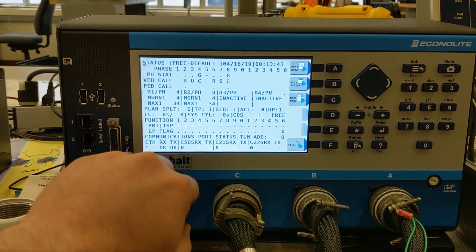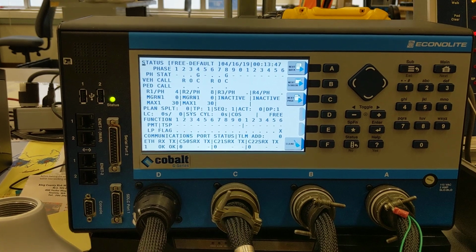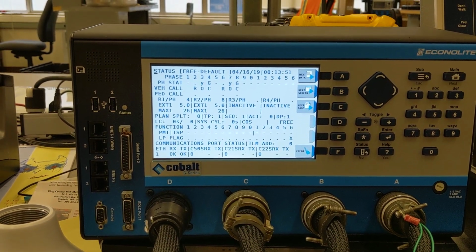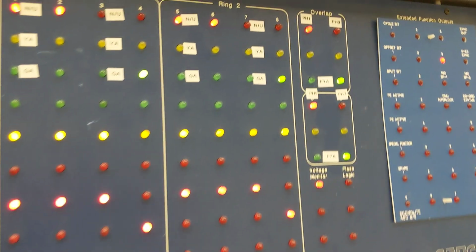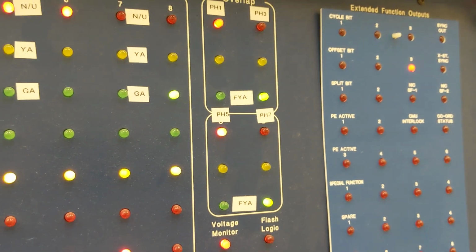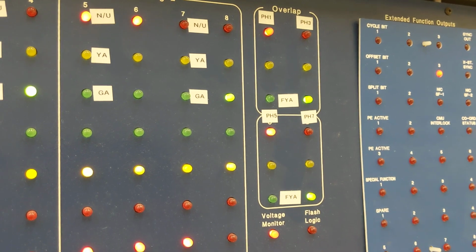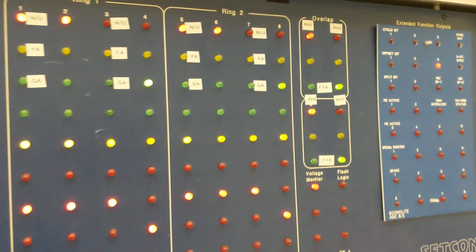We have flashing yellow arrow running on 4 and 8 with a delay. So there, 3 and 7, that lowercase y is representing the overlaps, running our flashing yellow arrow for phase 3 and phase 7. And that is on overlap B and overlap D, okay?